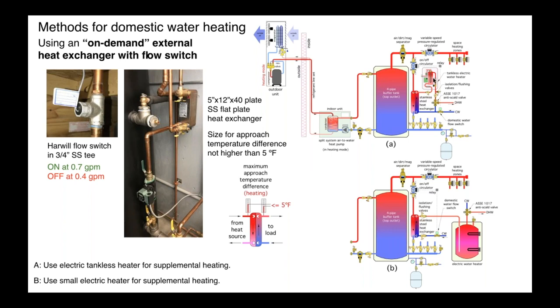We could boost it with a tankless water heater, or I just want to show another option, a small electric water heater. In my daughter's house, we use a 38-gallon water heater with a 4.5 kW element in it. And that element is actually large enough that if the heat pump was out of service for any reason, you still have a 4.5 kW heating element to supply the domestic water load.